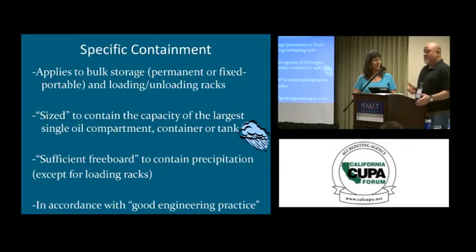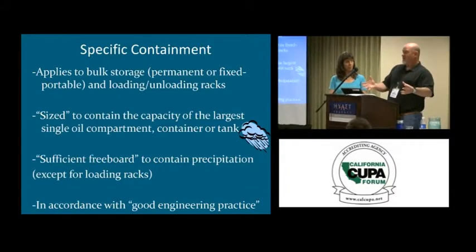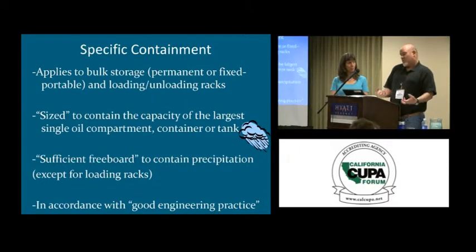Well, I think the nature of being an inspector is to question those aspects of the facility that look funky or lead to some concern of inadequacy or outright violation. A good example with 55-gallon drums would be the distinction between spill pallets and containment pallets, right? And we've all seen 4 drums sitting on a little pallet that's got some sort of capacity for collecting any spillage, or maybe sized even larger for containment.